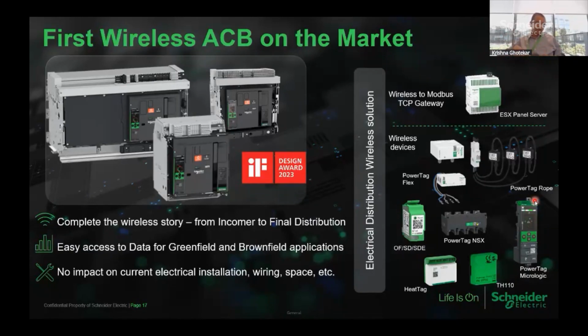But if there is a budget limitation, you will have a retrofit trip unit, not the standard trip unit, but a retrofit trip unit, which can be installed on NT NW breaker. Now the advantage here is, if you put a wireless trip unit on NT NW, it not only gets these digital parameters, ERMS, and so on, but on top of that, it also gets connectivity.